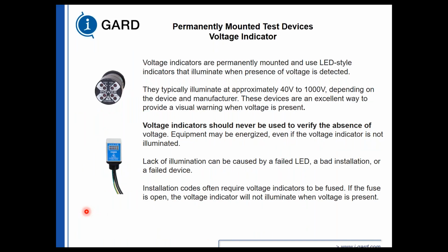These are permanently mounted test devices and they're voltage indicators, but they're presence of voltage indicators and not absence of voltage indicators. These lights come on when voltage is present. These lights are not on when the voltage is not present. They typically illuminate between 40 and 1,000 volts, depending on the manufacturer.